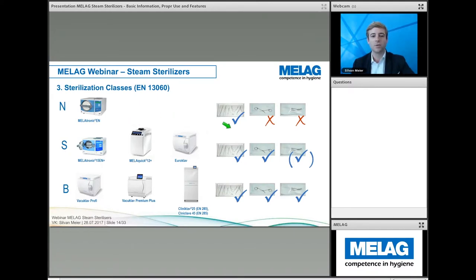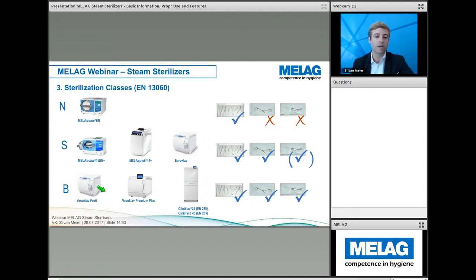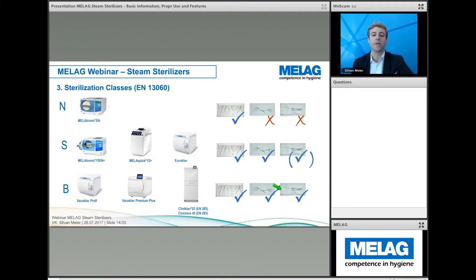Depending on the instruments used, different autoclaves can be selected. Class N is suitable for solid, simple instruments that are unwrapped. Class S — with the Melatronic, MelaQuick, and Euroklav — can sterilize solid instruments both unwrapped and wrapped, and depending on the manufacturer, some hollow instruments that are wrapped. Class B — with our Vacuklav from the Pro Class, the Premium Plus Evolution Series, and our hospital-sized Cliniclave — can sterilize all kinds of instruments, both wrapped and unwrapped, including very complex hollow instruments.